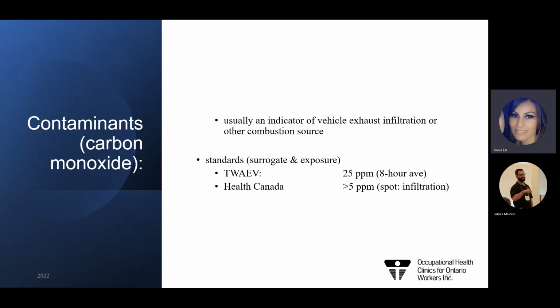With regards to carbon monoxide, which we also spoke about, this is usually an indicator of vehicle exhaust entrainment. It could be coming from your underground parking lot, or from a bordering parking lot on the exterior, with an outdoor air intake that's infiltrating vehicular exhaust from outside, or traffic on the nearby streets of your building. So you have to be very careful and recognize where our outdoor air intakes are coming in and where we're exhausting the air. That's why it's very important to know those things with regards to your building.